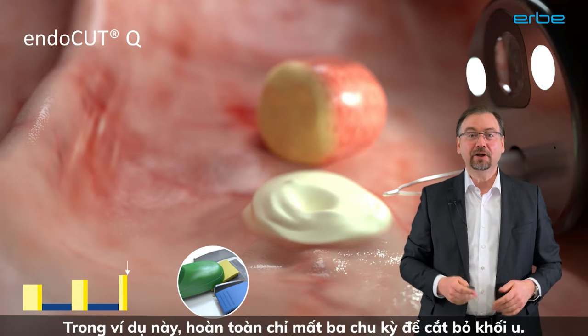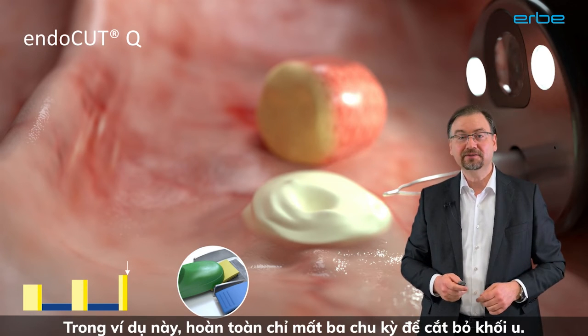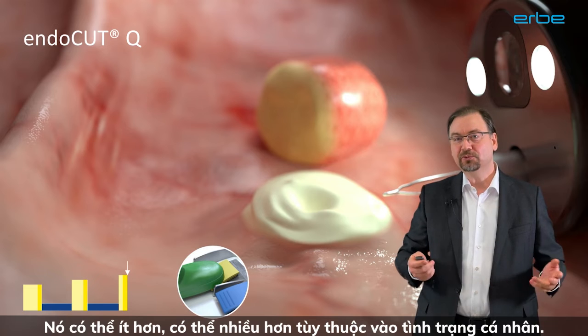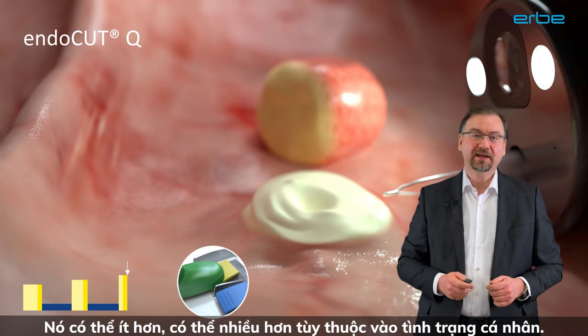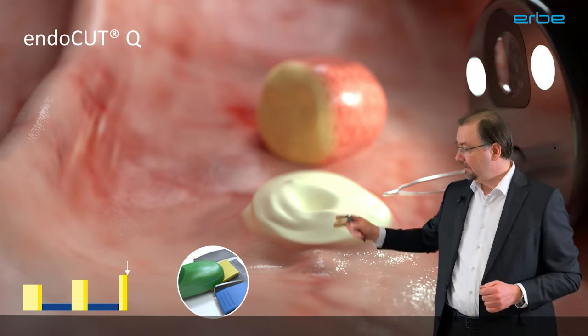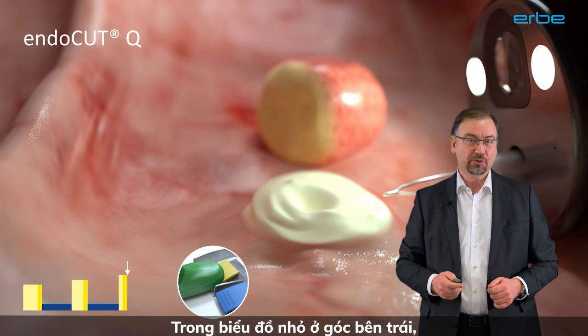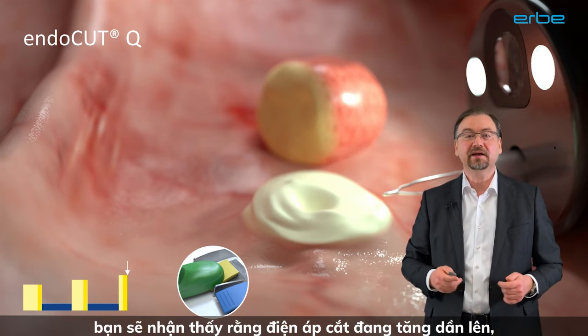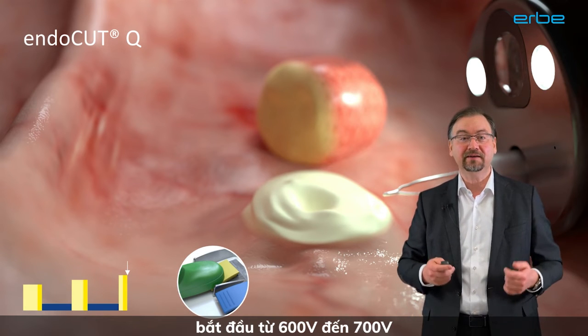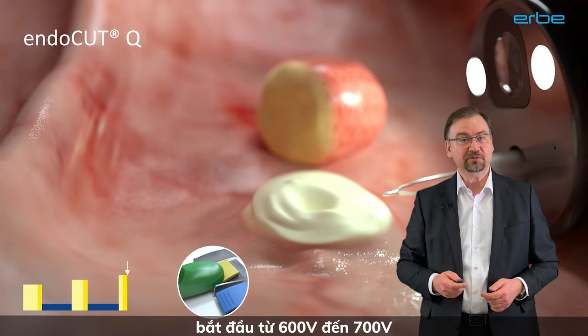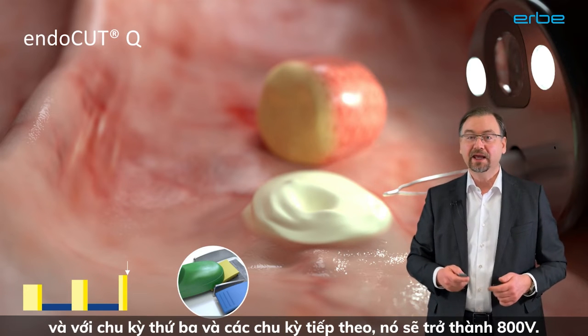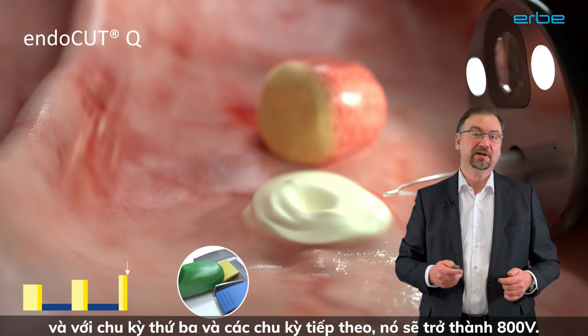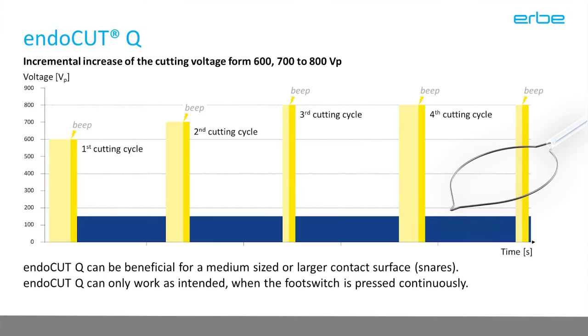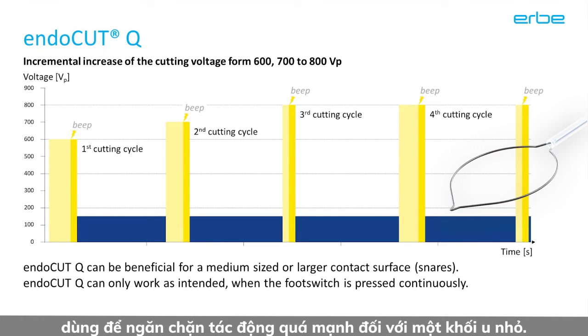In this example, altogether it took just 3 cycles to resect the polyp. Could be fewer, could be more, very much depending on the individual situation. In the little graph in the left corner, you will have noticed that the cutting voltage is rising incrementally, starting with 600 volts, then 700, and with the third and following cycles it becomes 800 volts. The lower voltage of the first cycles serves to prevent that the effect is too strong for a small polyp.